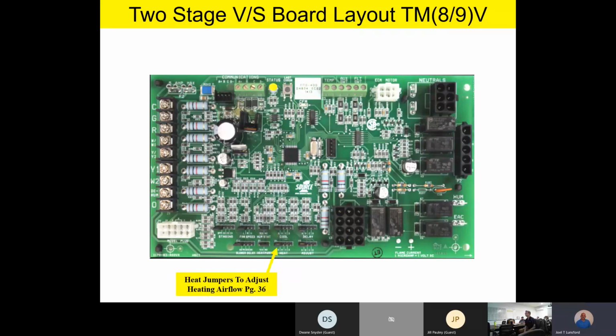Okay, so as we come down, we see we have a heating jumper on the control board, the heat jumper. The heating jumper, as its name implies, is to set up your heating airflow. From the factory, it's going to be set up to have the appropriate airflow for the heat exchanger and the size of the furnace. We always set these up at the maximum airflow, because we don't know what your duct system is going to be like out in the field. But to optimize your heating airflow, be sure and take a look at the data plate on the furnace. You may want to make some adjustments, especially if you have a really nice, wide open duct system with very low restriction. You may want to adjust that a little bit for ultimate comfort.